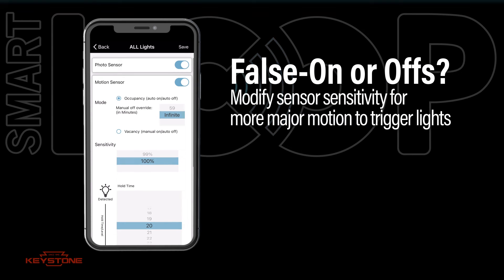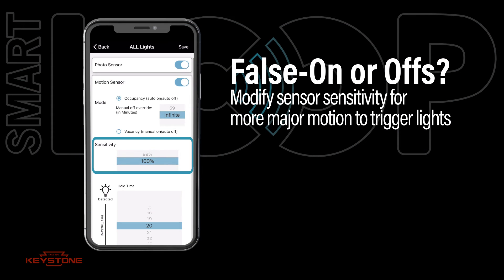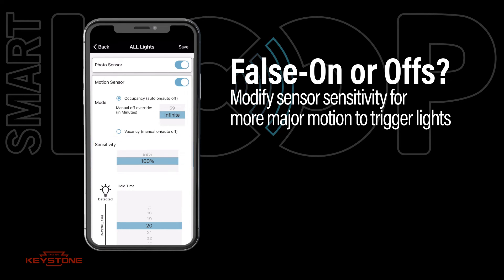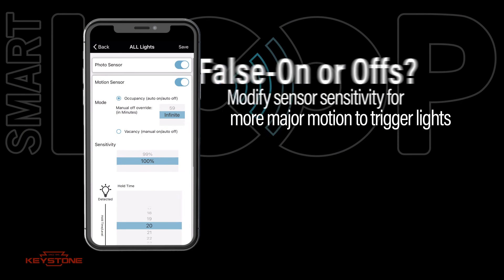If you are experiencing false ons, the sensor sensitivity may be too high. You can reduce this so the sensor requires more major motion events to be triggered. Adjust the sensitivity of the motion sensor by scrolling the sensitivity percentage settings.